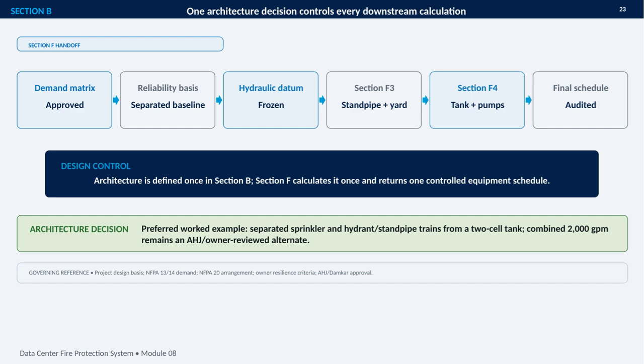A combined 2,000 gallon per minute arrangement is still identified as an alternate, but it requires review by the authority having jurisdiction and the owner. So, it is not the controlling basis for this workflow. The governing references are the project design basis, NFPA 13 and NFPA 14 demand requirements, NFPA 20 pump arrangements, the owner's resilience criteria, and final AHJ or Damker approval. Together, these controls keep the calculations traceable and prevent architecture changes from propagating unnoticed.